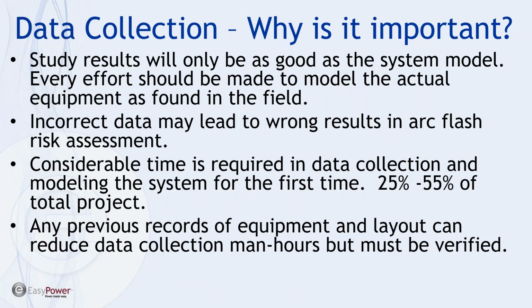So it becomes obvious once you play with this a little bit that it is an important step, insofar as the data I collect needs to be as accurate as possible. Especially in an existing facility, it's almost a snap in new construction because we have exact lengths and exact documentation on the equipment. If we're talking about an older facility that could be 25 years or older, it's going to be very difficult to get some information on some of the equipment. At that point, you're left to make some assumptions and do some estimations. These need to be documented, and it's worth spending some time trying to recover any previously detailed as-built or maintenance records or repair systems. Anything you can collect should be included as you're starting the data collection process.